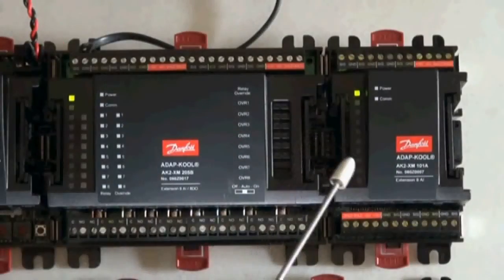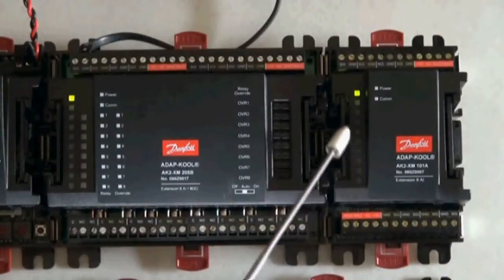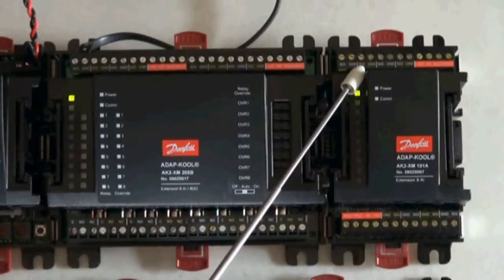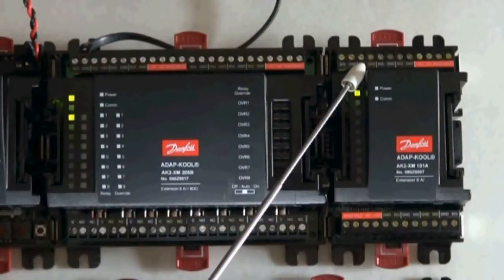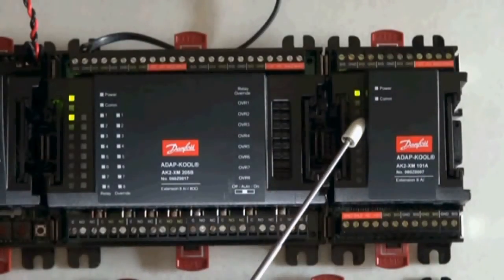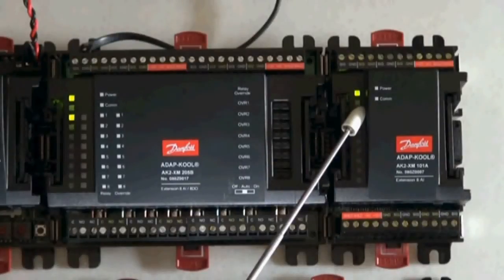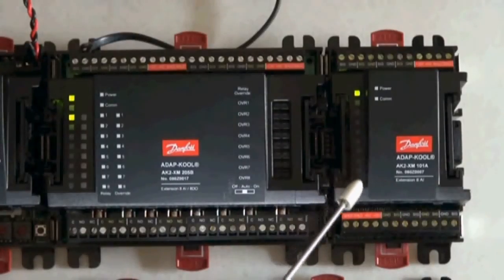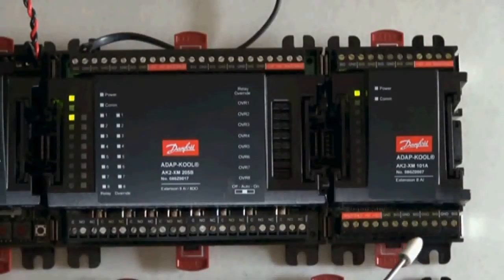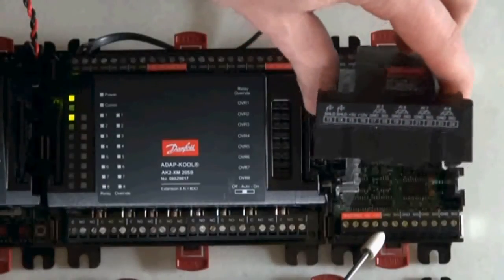Next, moving to the analog input board, you see a very similar arrangement for inputs. The COM light would turn red if there's a communication problem with the AK2-55. The bottom row also contains inputs, but in a reversed fashion. When in doubt, remove the cover and look at the legend on the bottom if there's a question about wire hookup.